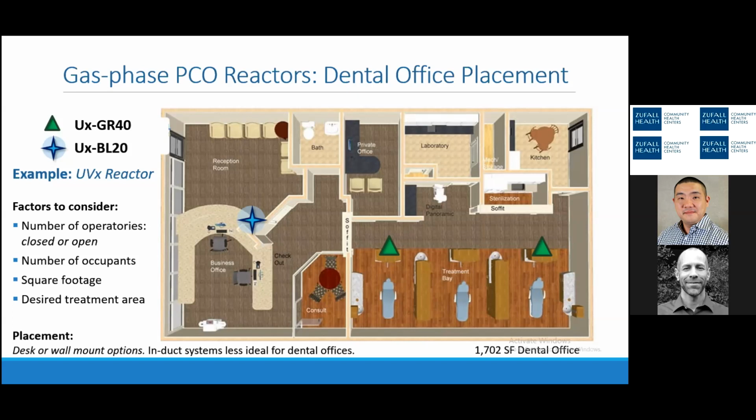And what we have been recommending for dental offices is the use of these essentially standalone units that could either be mounted on a wall or placed on a desk, as opposed to in-duct systems. The in-duct systems are essentially less ideal because in these dental offices, you tend to have areas where there's a concentration of aerosols, essentially the operatories, and then you have other areas where there are no procedures occurring, and you're basically just trying to treat the area for the number of occupants.